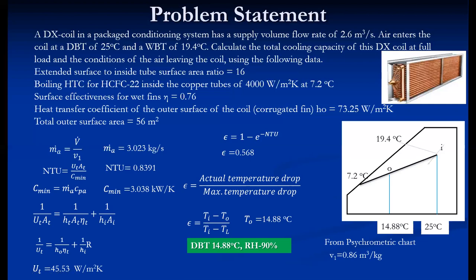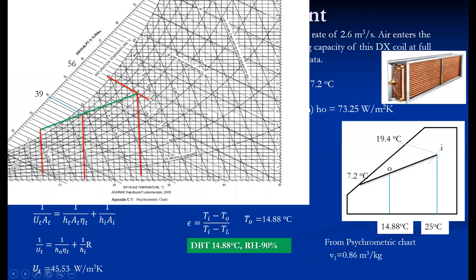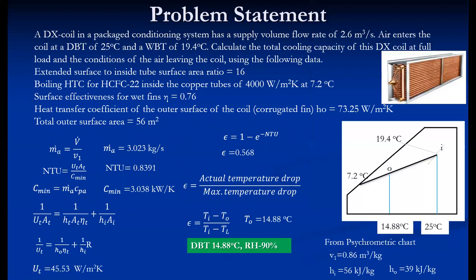From the psychrometric chart, the exit conditions are DBT = 14.88°C and relative humidity = 90%. To calculate cooling capacity, we need enthalpies at inlet and outlet: h_i ≈ 56 kJ/kg and h_o ≈ 39 kJ/kg from the psychrometric chart. Q_L = m_a · (h_i − h_o) = 3.023 × (56 − 39) ≈ 51.39 kW. This gives us both the total cooling capacity and the exit conditions of the DX coil.